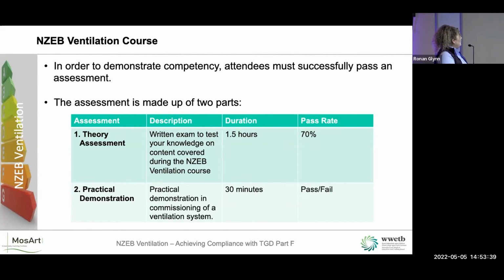So to make it fairer, then we have a practical demonstration as well. That's 30 minutes one-on-one, and that is how can you balance a ventilation system? So the 30 minutes to balance it, to adjust the diffusers until the supply and the extract are equal, or if they're not equal, they have to be done in compliance with Part F, which states that the supply can be no more than 15% higher than extract. And the reason for that is we'd rather be in a bit of positive pressure and pushing out the toxins than negative pressure, holding on to the likes of radon or VOCs in our house. So that's really important. So that's simple pass fail. Pass rate for that is very, very, very high. Okay.